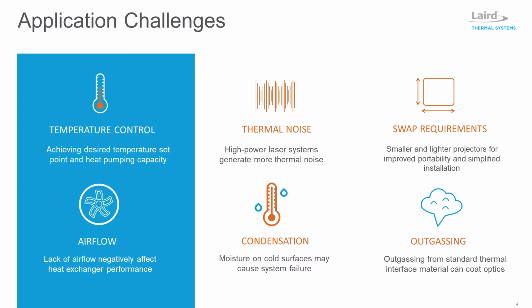As the temperature of optoelectronic components drops below dew point, moisture will form on cold surfaces and potentially seep into the electronics, causing system failure. It is therefore important to protect electronics against condensation. Because epoxy or RTV sealant of thermoelectric coolers is not sufficient insulation, it is recommended to have a secondary insulation barrier to protect the thermoelectric cooler cavity.